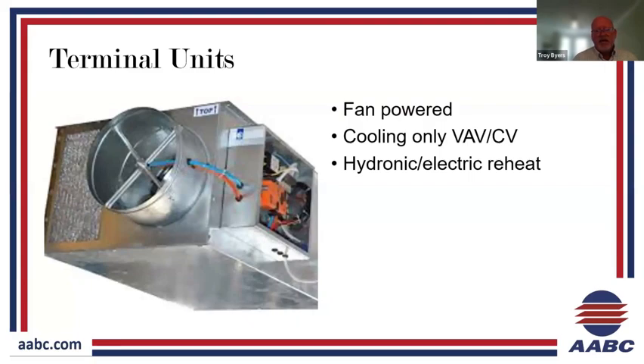And so then we're also looking at capacities, both airflow, meaning go ahead and take that VAV box to its maximum CFM setting, measure, minimum CFM setting, measure, make sure it's controlling between minimum and maximum. And also for any reheat, measuring the capacities there. Again, it could be hot water reheat, measuring the entering and leaving water temps, water flow rates, and then entering and leaving air temperatures. On the electric side, we would also be looking at measuring the kW of the heater, making sure we're matched up with the rated kW, and then any staging that's required by the electric heat to determine if that's sequencing properly.